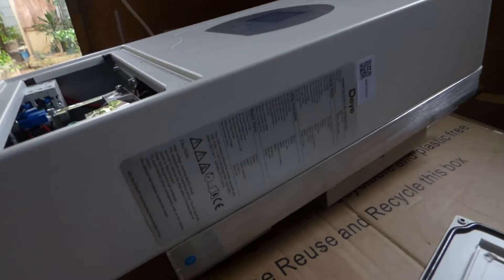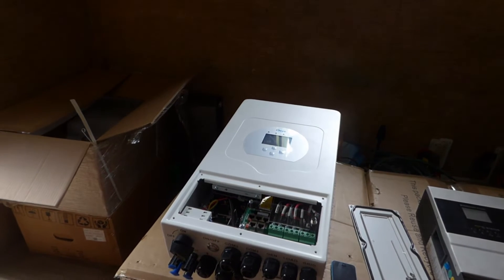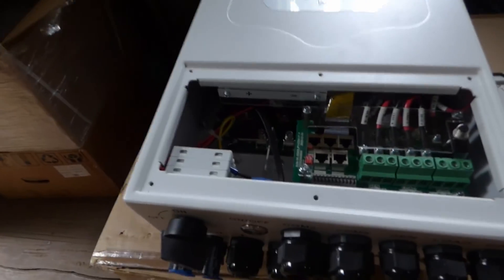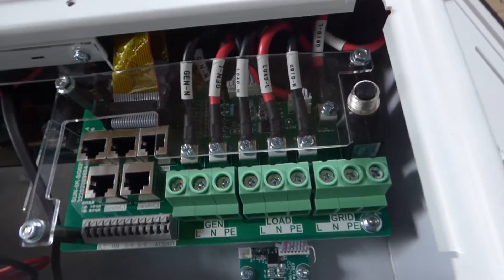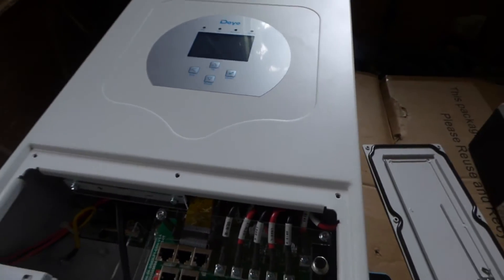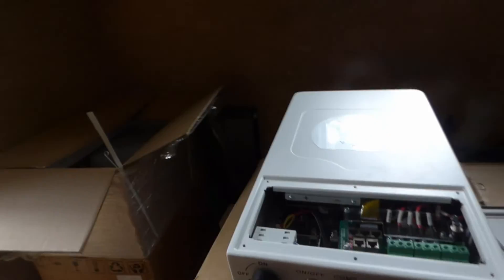On the PV side, I believe this is limited to 3,500 watts — I'll correct it in my next video if I'm wrong — and you have dual MPPTs. Looking inside, you can see very good quality connections and blocks. You have a generator input, a load output, and a grid connection. The surge is 7.2 kilowatts. There's a dedicated on/off switch for the PV — we didn't have that with the Growatt — and a dedicated button to turn the inverter on and off.